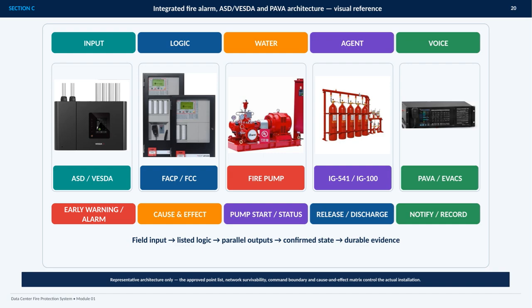Water protection is represented by the fire pump, including pump start and status. Agent protection is represented by IG-541 or IG-100 release and discharge. Voice functions are handled through PAVA or EVACS for notification and evacuation messaging. Together, these paths support early warning, alarm, suppression, release control, and event recording.